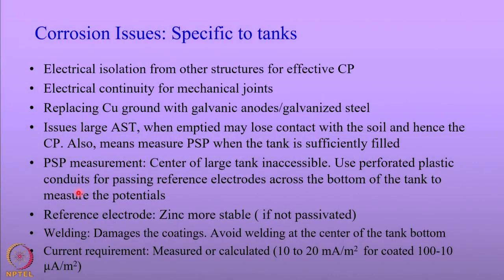Let us look at the specific issues applicable to storage tanks. The storage tanks store process liquids, so there are inlet and outlet pipelines. These pipelines need to be electrically isolated, or if not, we need to look at them as a composite structure when designing the cathodic protection system.